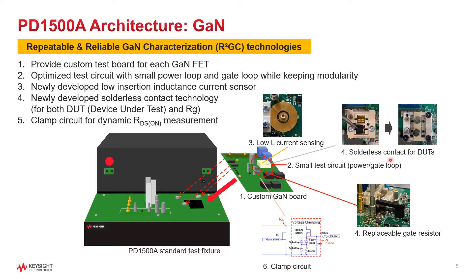Another R2GC technology is the solderless contact technology for both DUTs and gate resistors, which makes it much easier to test multiple samples under multiple RG conditions. We also developed a clamp circuit to evaluate dynamic RDS-ON within hundreds of nanoseconds after the switch event.